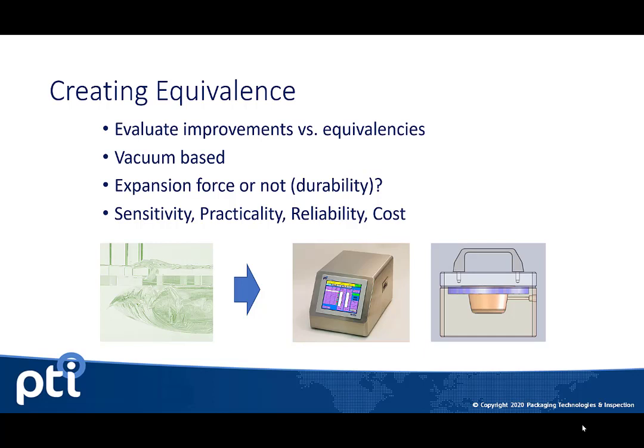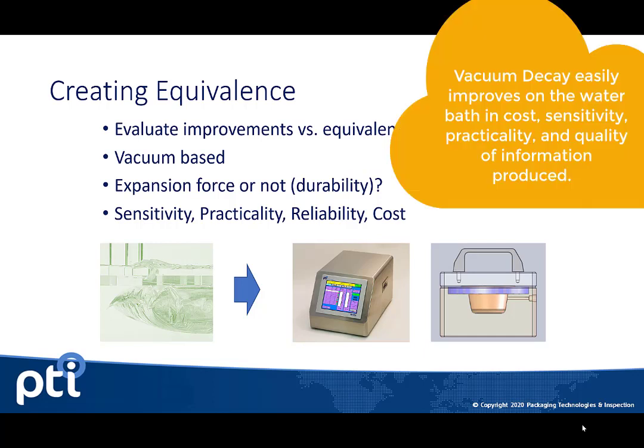So when looking at the water bath, we have to really ask ourselves all about that method and what it's doing to the package. What is it exposing the package to? We also see that it's a vacuum-based method. So on a flexible package, it is applying some sort of stress to the package walls. And that's perhaps a valuable test that you may want to consider. So we have to meet the sensitivity, the practicality, and the reliability of that water bath. Matching the cost is also a very important consideration.